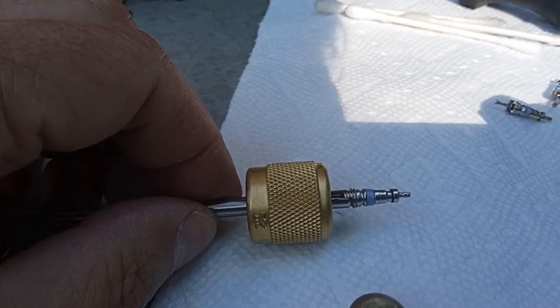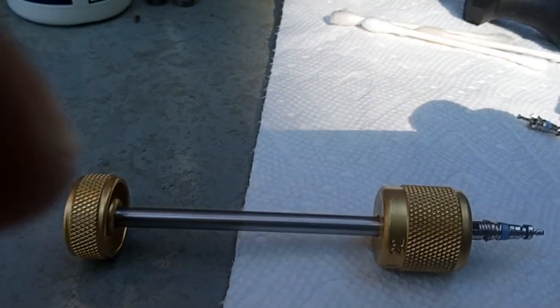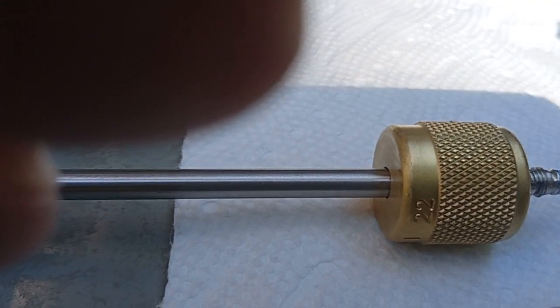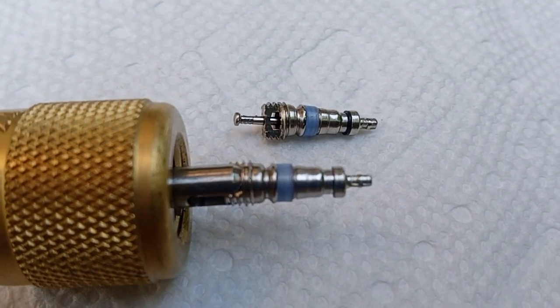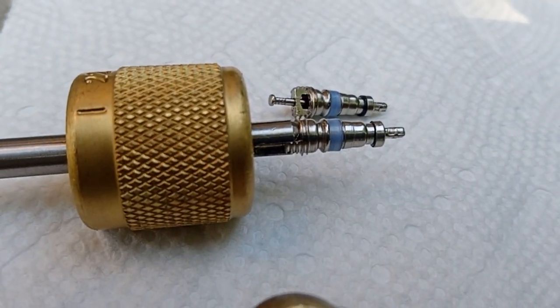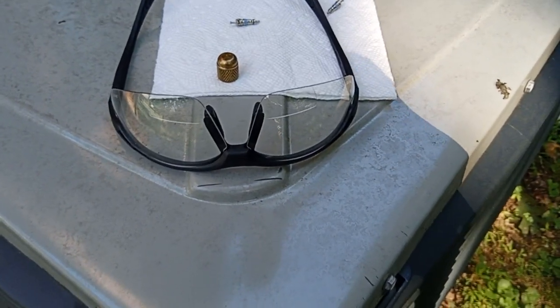I don't see a thing wrong with that core, but it was leaking. Why? Does something about that look different than this? I don't know, but I think the seal's damaged. See the seal on the end — the one laying on the paper towel. See how the black is showing out, and on the new one it isn't. I don't know exactly what caused that or what it means. And the most important tool: safety glasses — regular glasses off, safety glasses on.